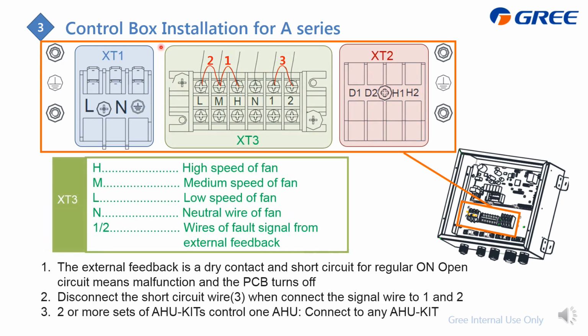As for the XT3, this is for the control of the fan motor. And also you can find that there's a low, medium, high, and this is the neutral. For this one, we only support the AC fan motor. And you can find that this is already a short circuit. If you just have a mounted fan speed, you can take it off. And here the 1 and 2 is for the error feedback.